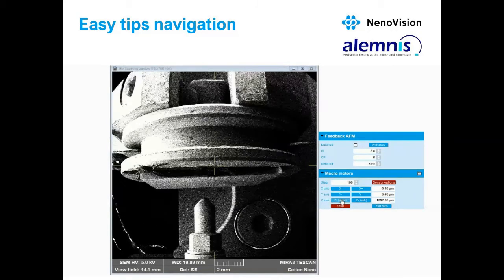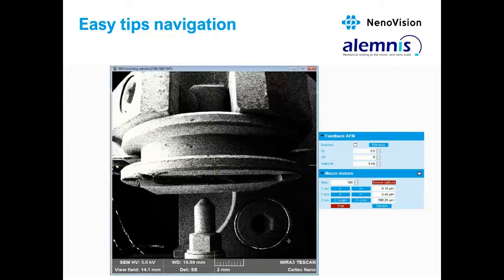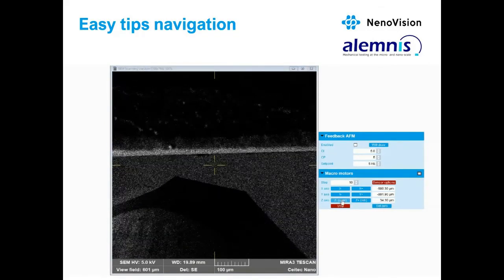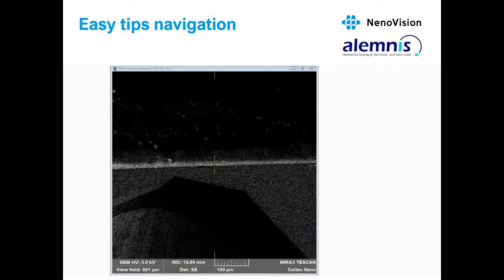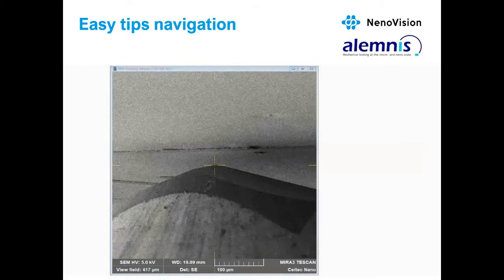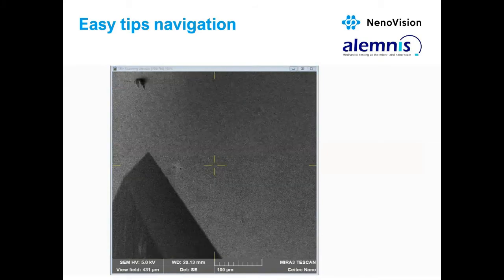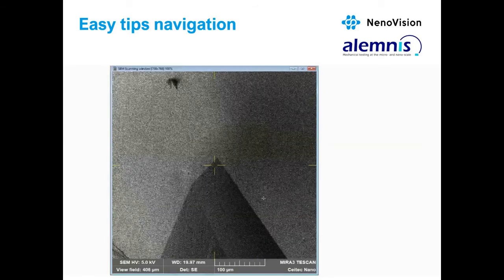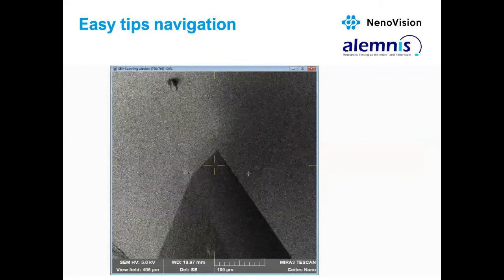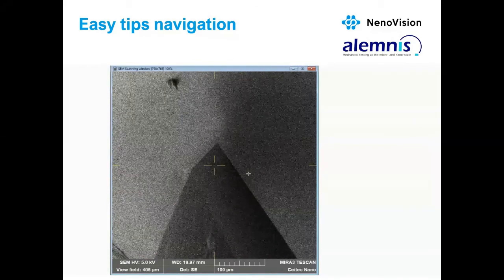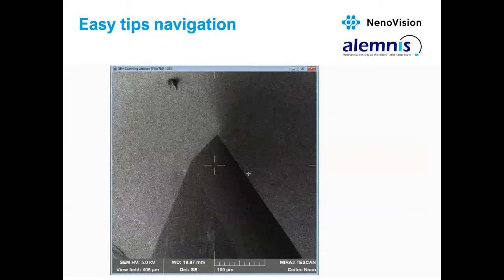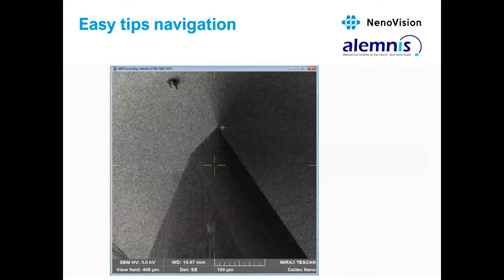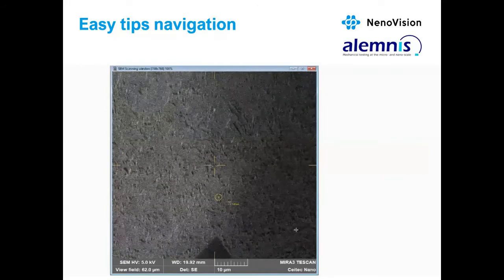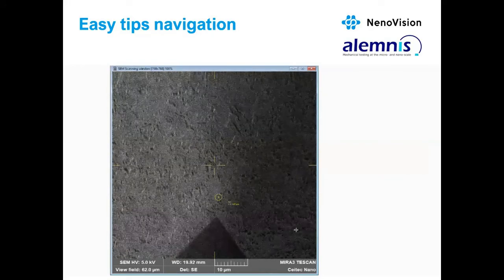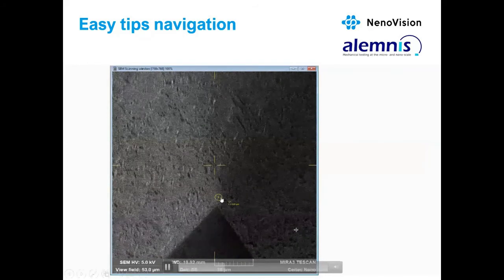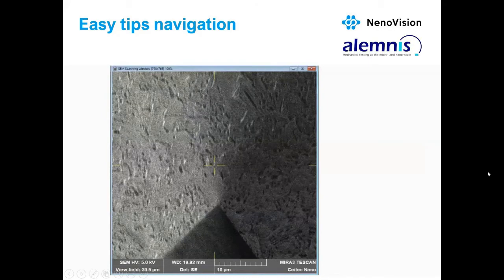We first get closer with the sample to the indentation tip. It's quite easy because you can see all the time in the SEM. We find the spot to be investigated, and then we slowly get into the contact. From the shadow effect, you can see that we are getting very close to the sample. As you can see, this little circle here is the place where we would like to make the indent.